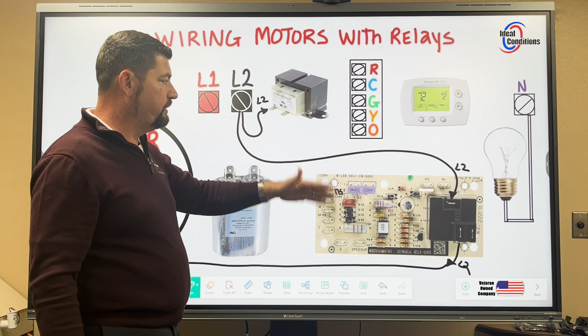And see, that's a much safer way than bouncing from component to component, because if I'm going from component to component, then I might be going from L1 to L2, L1 to L2, and it's real easy to cross paths, because it's harder to inspect something like that, especially when you're working above your head in an air handler where you might be standing on a stool, but it's definitely probably going to be dark. It's going to be a cramped work area. You're going to have tools in your hand.